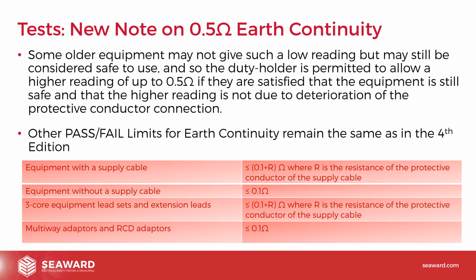But realistically, from my point of view, don't think too heavily about it. Still use your 0.1 plus R. And as I've put there on the slides, the pass-fail limit for earth continuity remains the same as the 4th edition. It's still the 0.1 plus R. There's nothing that's changed in there. The only addition is under the table in the notes, they've put this little mention in there about the 0.5 ohm.